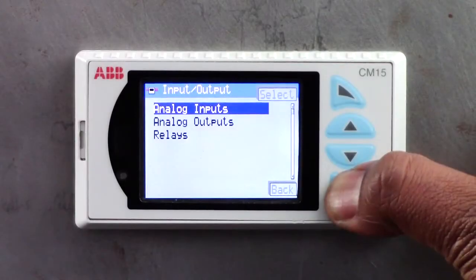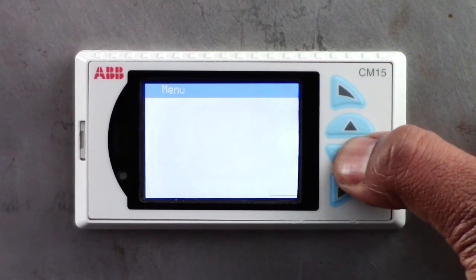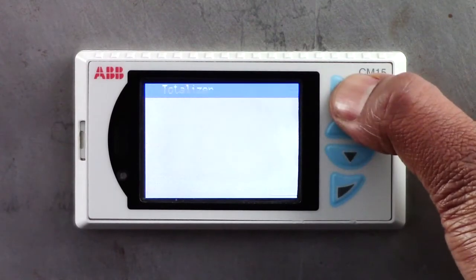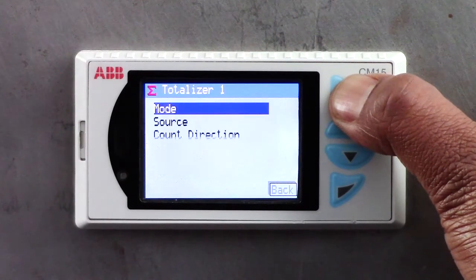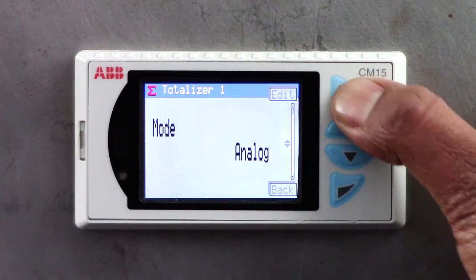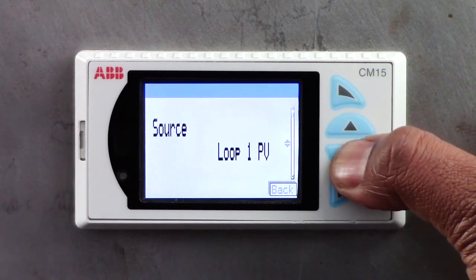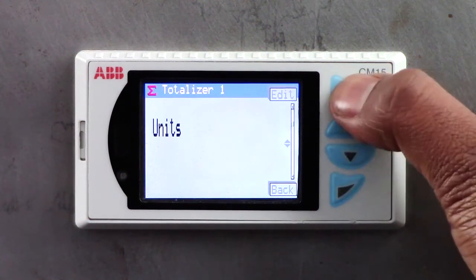Now navigate to the totalizer menu option to complete the totalizer setup. For the CM15's totalizer to count correctly, the totalizer's mode must match the selected input type. In this case the mode needs to be set as analogue. Also select the appropriate source, count direction and units.